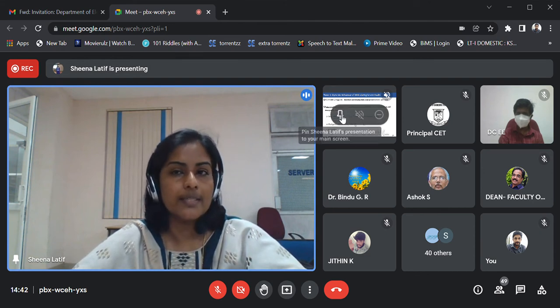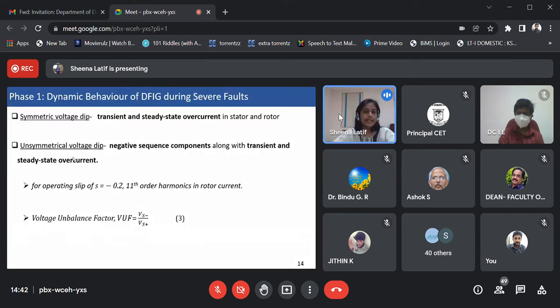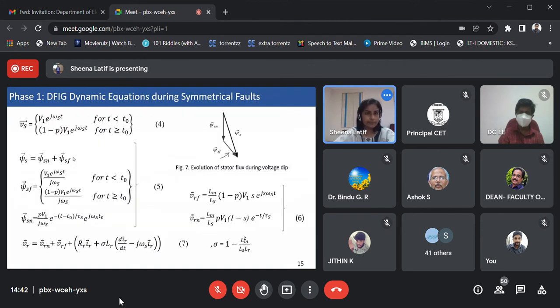Dynamic behavior of a DFIG during severe faults. During severe symmetrical voltage dip conditions, transient and steady state overcurrent occurs in the stator as well as the rotor. Whereas in the unsymmetrical voltage dip condition, together with the transient and steady state overcurrent, there is a negative sequence component present in the rotor currents. For the operating slip of s equal to minus 0.2, it is the 11th order harmonic that occurs in the rotor current during unsymmetrical voltage dip conditions. In unsymmetrical voltage dip conditions, we can see another factor, the voltage unbalance factor, given by Vs minus divided by Vs plus.